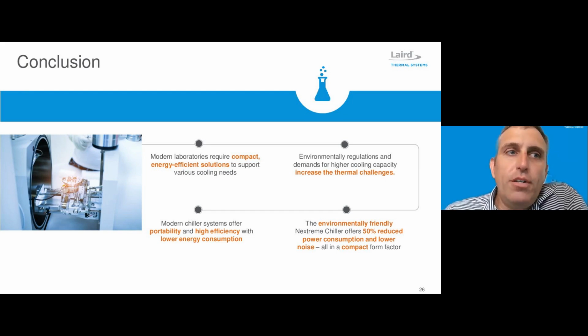So when we look in summary, there's a number of applications that require cooling within laboratories. A lot of the instruments that are used today are becoming more and more powerful and becoming smaller. So what does this mean? This means higher heat densities, more cooling required, and as a result, liquid cooling has become widely accepted within laboratories. Chillers are an efficient solution for this. They can provide much more precise temperature and flow rate over a tap water or a central facility system. And the systems are also much more mobile. So when they can be used in one lab and then need to be removed to the next, it's very simple. It doesn't require any plumbing in terms of bringing those cooling lines over to the new application.